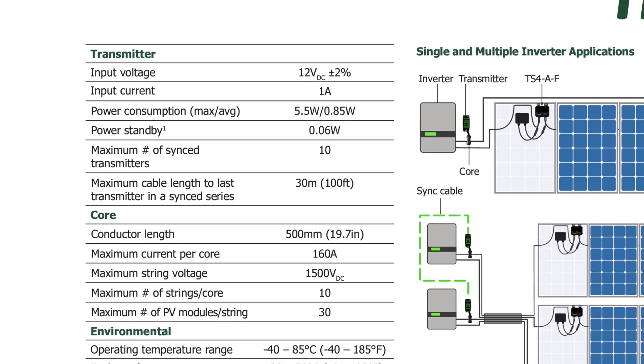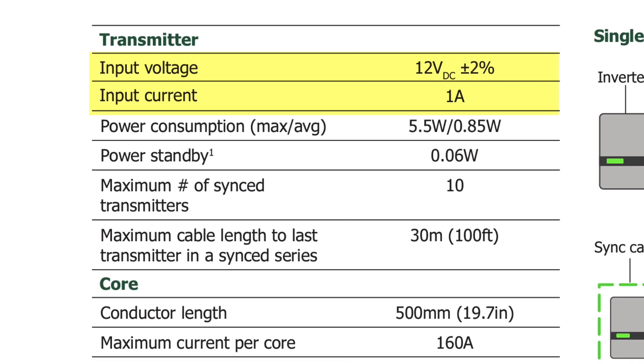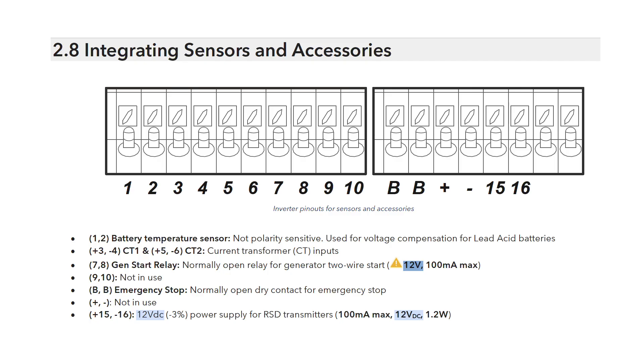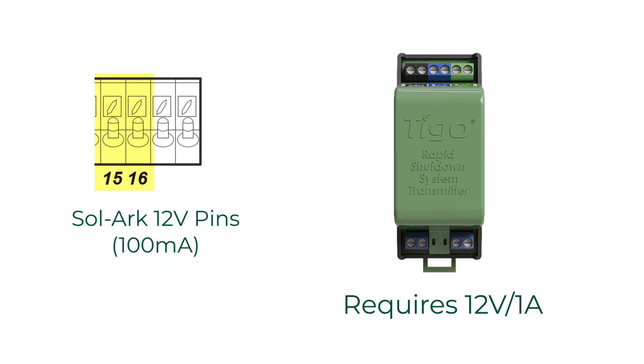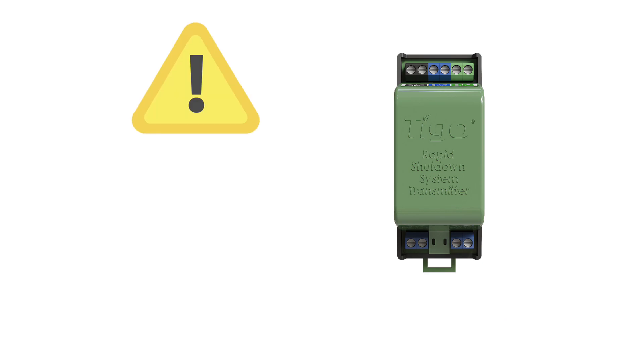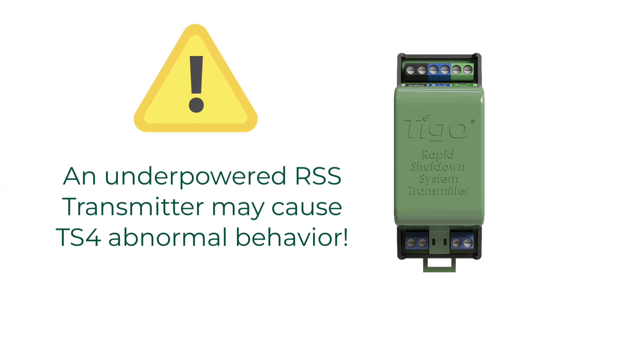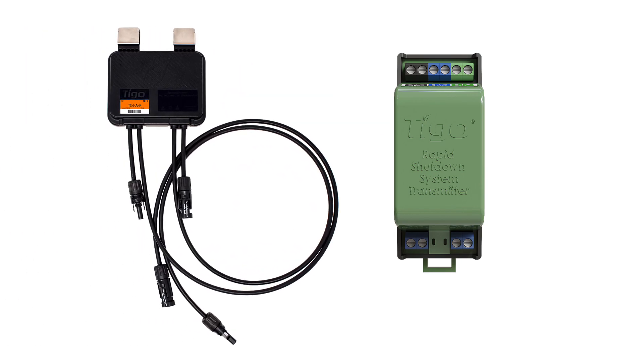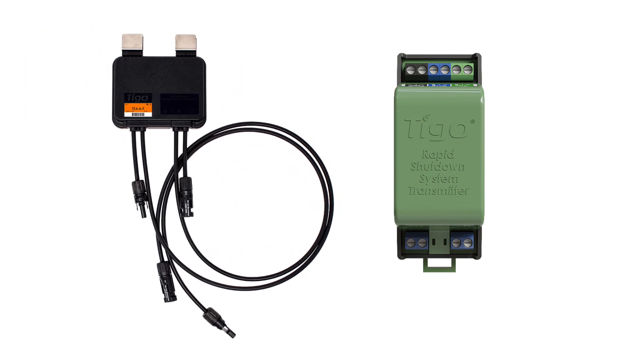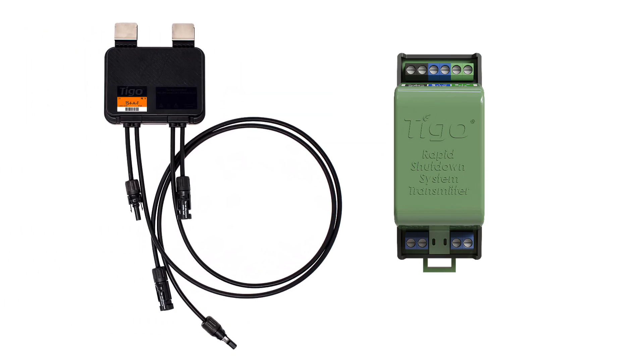The RSS transmitter data sheet states the power requirements as 12 volts and 1 amp. Therefore, the internal 12-volt pins of the Solark inverter are insufficient. If the RSS transmitter is underpowered, the TS4 may exhibit abnormal behavior and enter and exit rapid shutdown mode at random intervals. This behavior results in reduced array output and, eventually, TS4 failure.